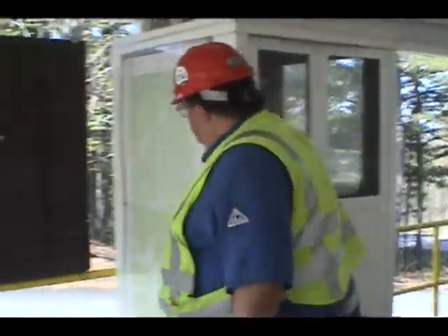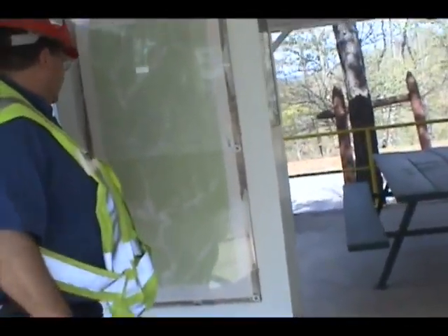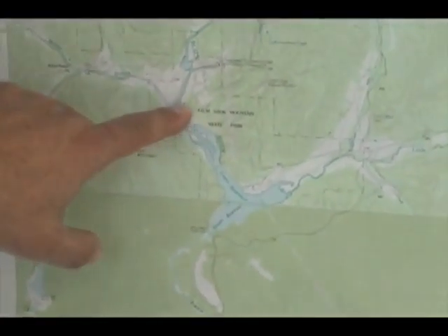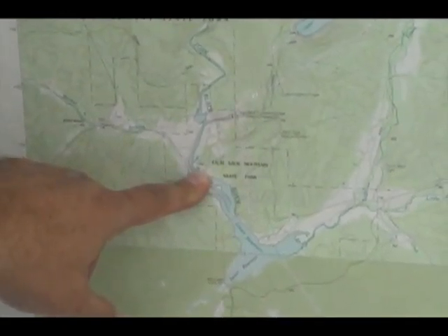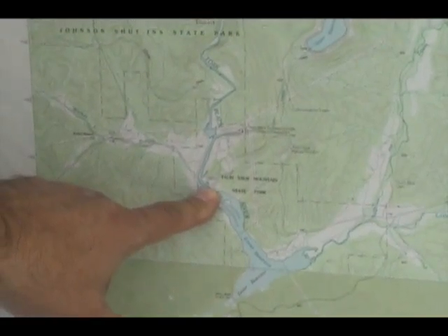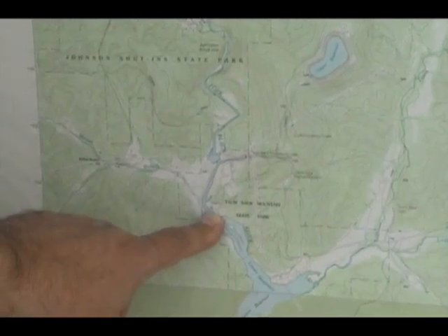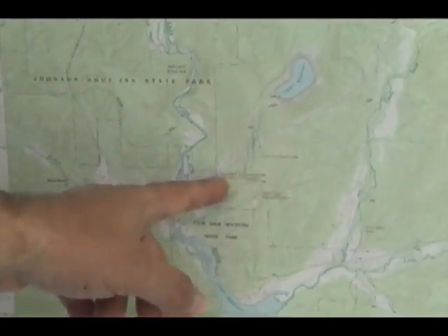Sure, that'd be great. You won't be able to film this because you won't be able to capture the details, but here's an actual topo map that showed, this is the Lower Reservoir Dam. This is our lower reservoir. At full pool, it has 390 surface acres. When we are pumped back, we change the surface acres. We go down to approximately 200 surface acres. So we decrease the surface acreage by about half when we pump back, and that's 13.5 vertical feet of elevation that we change. Gotcha.